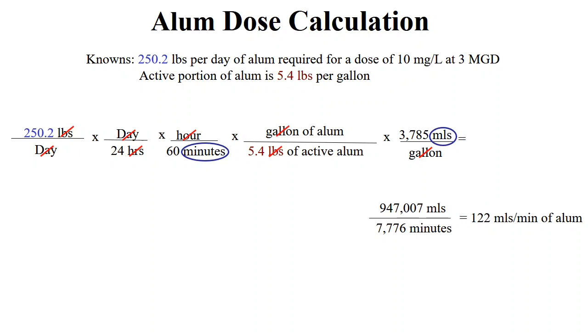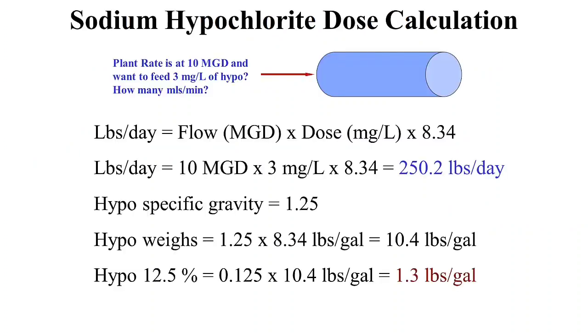That achieves a dose of 10 milligrams per liter at a plant operating at 3 million gallons per day. Here's another example for feeding sodium hypochlorite, or hypo, at a dose of 3 milligrams per liter at a plant operating at 10 million gallons per day. Following the same procedure, we get the same feed rate of 250 pounds per day. This hypo has a specific gravity of 1.25; multiplying by 8.34, a gallon of hypo weighs about 10.4 pounds. The hypo is 12.5%, so 0.125 times 10.4 shows the active ingredient is 1.3 pounds per gallon.